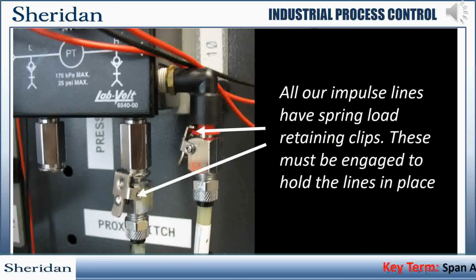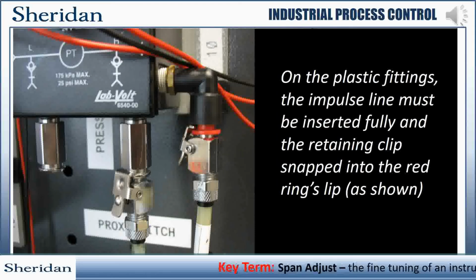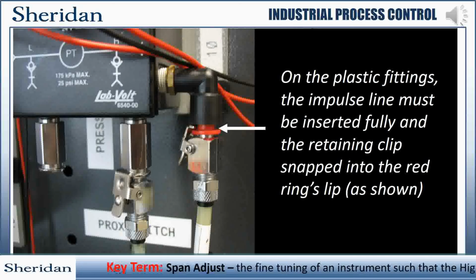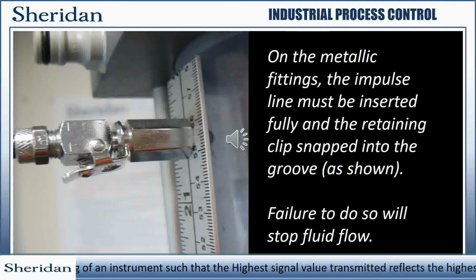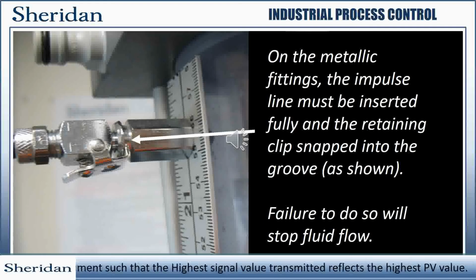All of the impulse lines used in our labs have spring-loaded retaining clips. These must be engaged properly to hold the lines in place and to release the spring-loaded internal check valve so that the fluid can flow. On the plastic fittings, you will find a red plastic retention ring. The impulse lines must be inserted far enough that the spring clip can engage with the red clip. Like the plastic quick connect ports, the metallic ones have a retention feature, but here it is a machined groove. The impulse lines must be retained by this groove to overcome the internal check valve and to ensure proper reading.